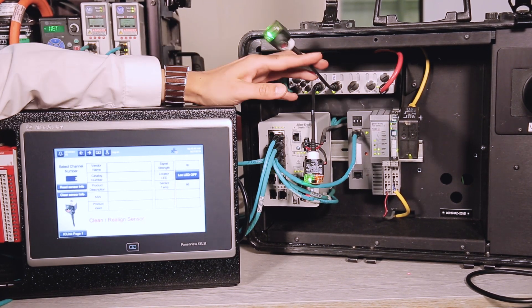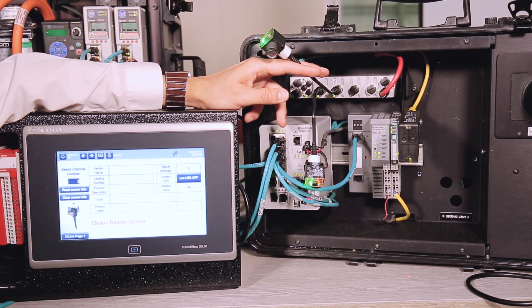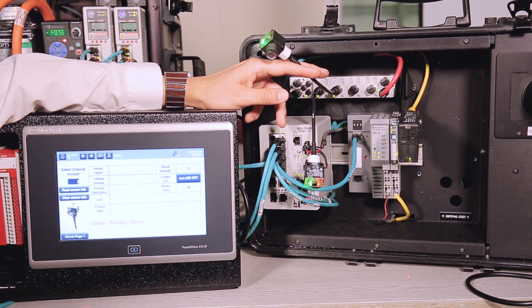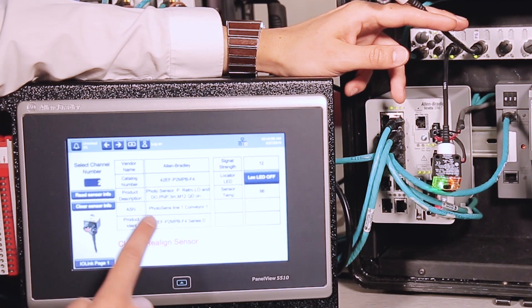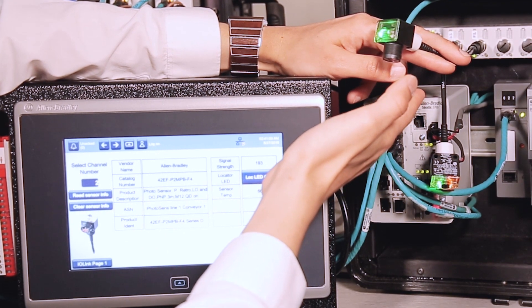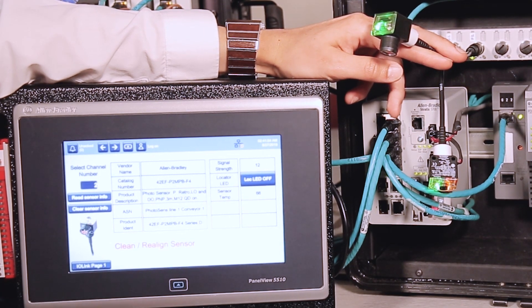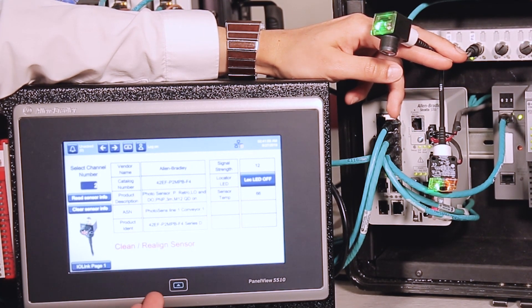So here we have a photoelectric sensor which is sat on IO-Link. We can take all the sensor information out of that, which includes the vendor, the catalogue number, product description. We also take the signal strength of the sensor as well, and this allows us to do such things as make people aware of when a sensor has either gone out of alignment or might need cleaning.